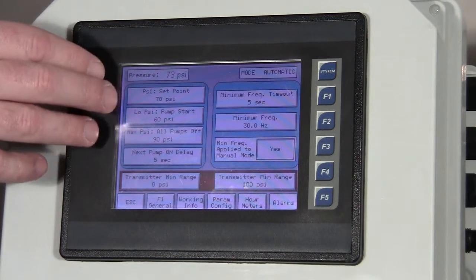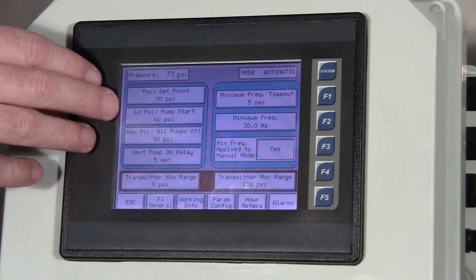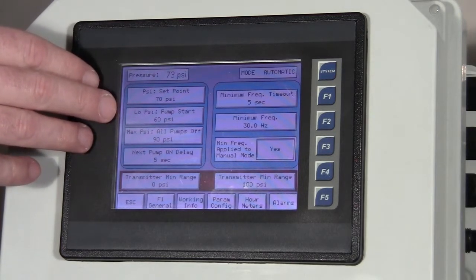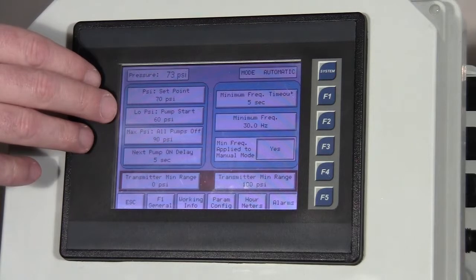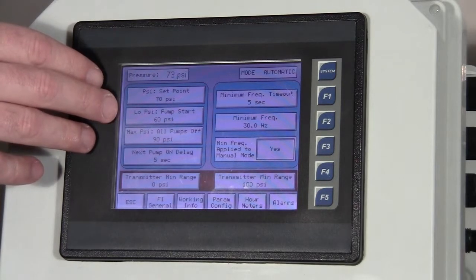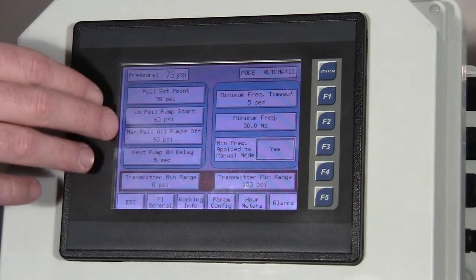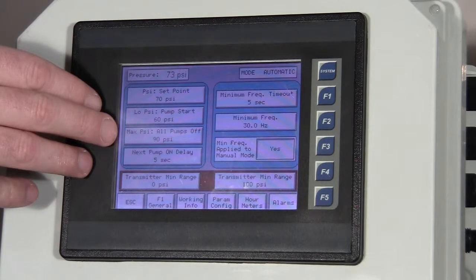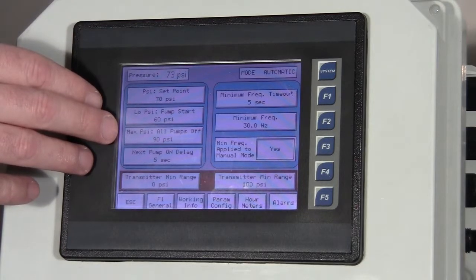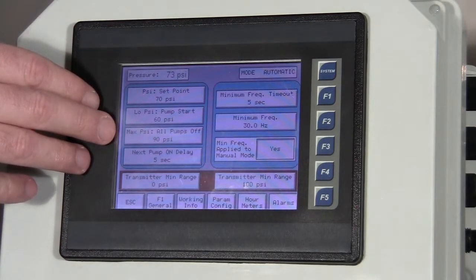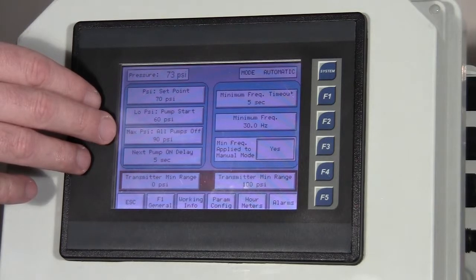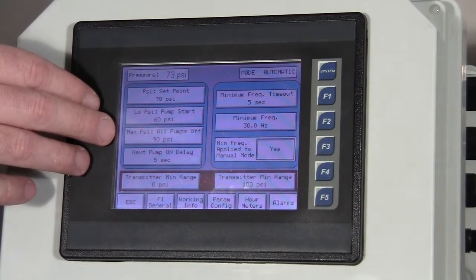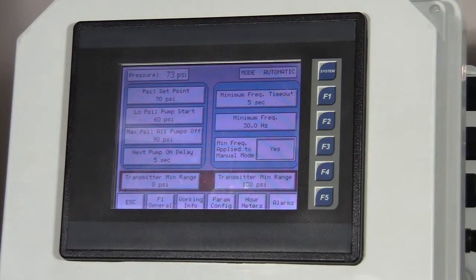We have a low pressure setting, and this is our setting that triggers a pump to come on. And then we also have a max pressure setting. And this is a safety feature, which if our pressure reaches this max limit, which right now it's set to 90, if it reaches that max limit, it turns all three of the pumps off.